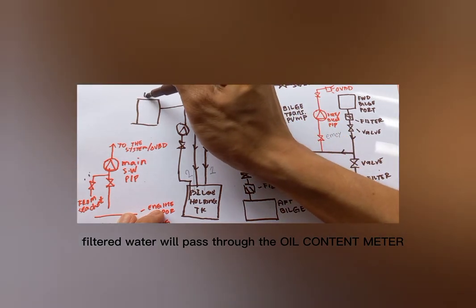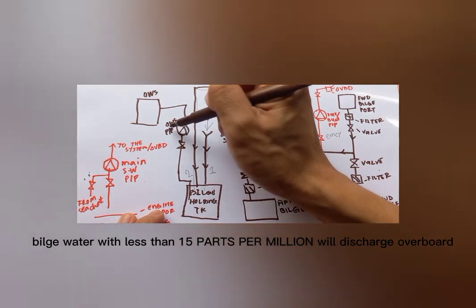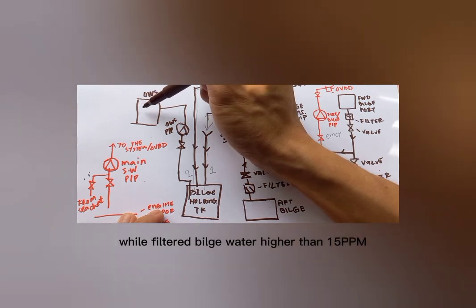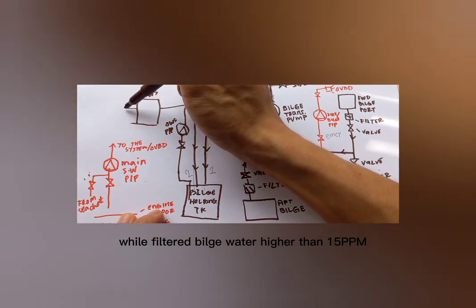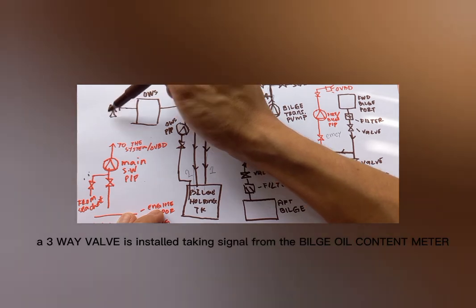Filtered water will pass through the oil content meter. Bilge water with less than 15 parts per million will discharge overboard, while filtered bilge water higher than 15 ppm will send back to the bilge holding tank. A three-way valve is installed taking signal from the bilge oil content meter.